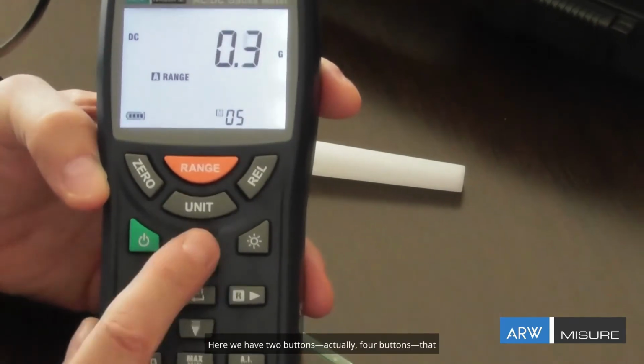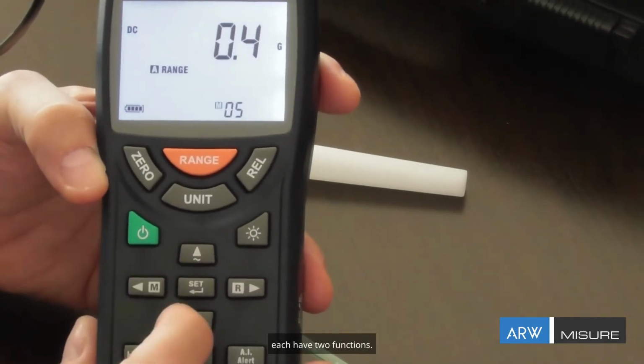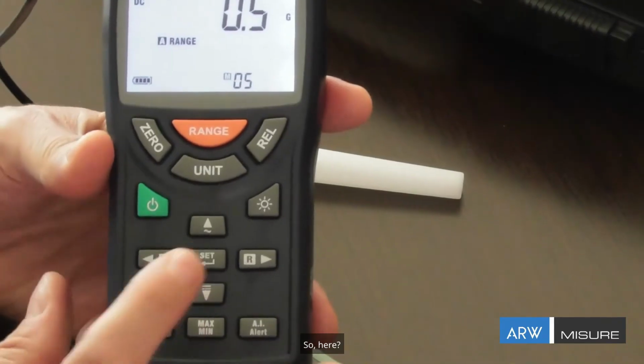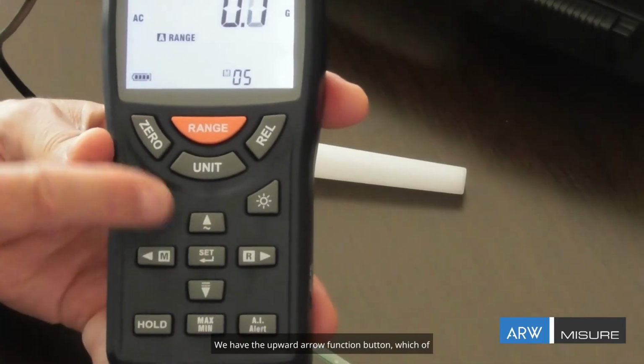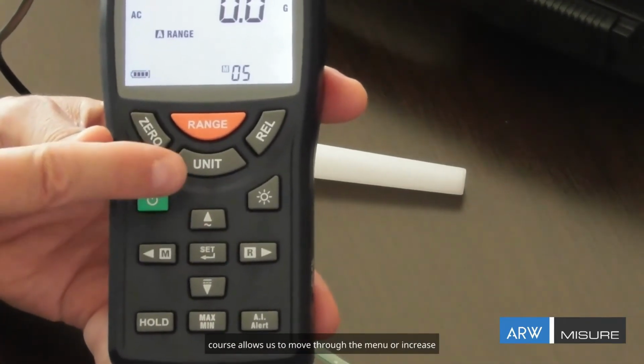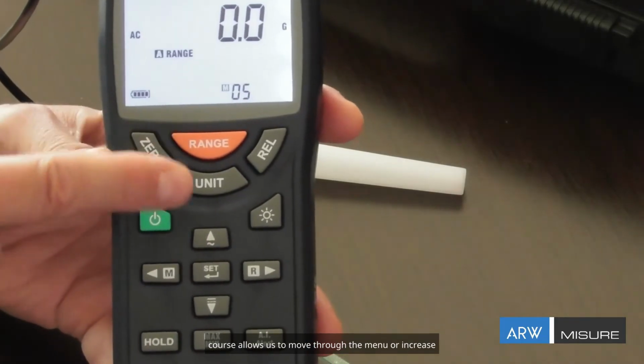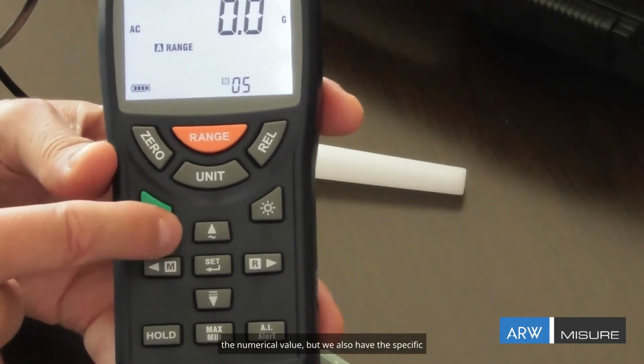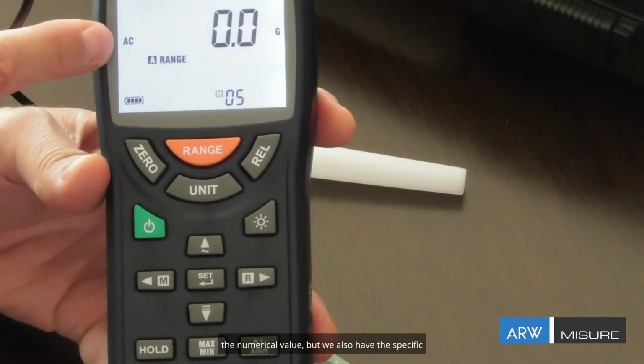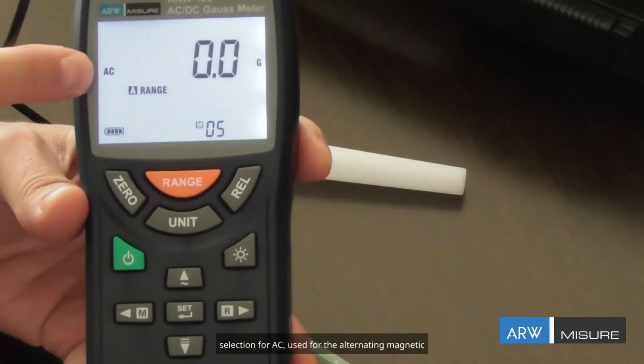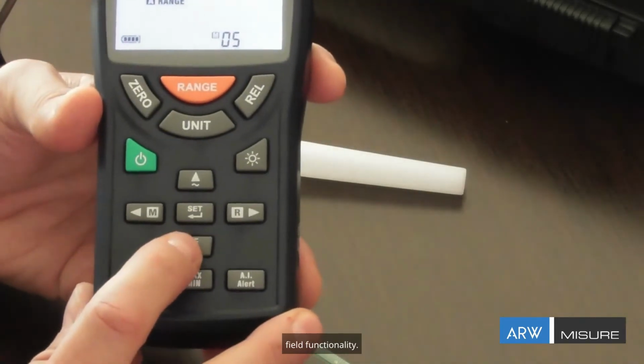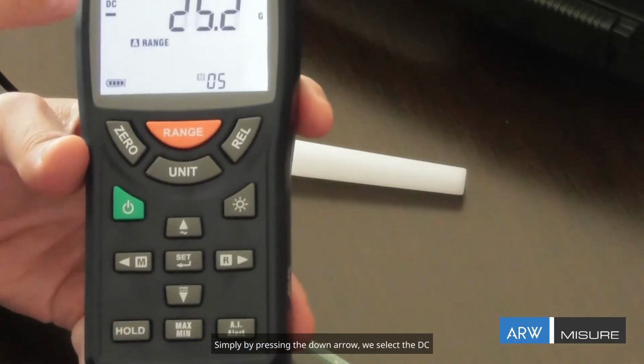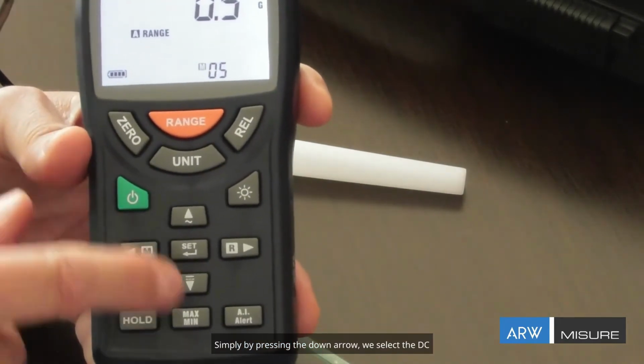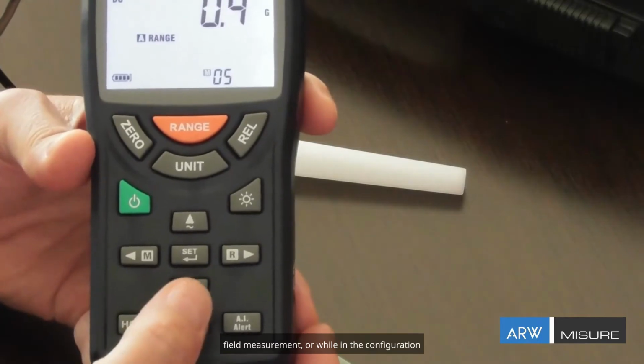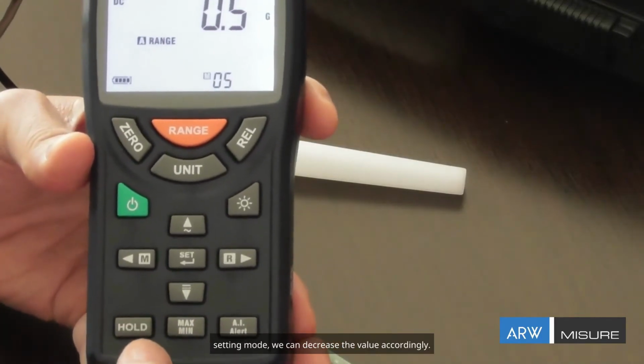Here we have 2 buttons, actually 4 buttons, that each have 2 functions. The upward arrow button allows us to move through the menu or increase the numerical value, and also provides the specific selection for AC, used for the alternating magnetic field functionality. Pressing the down arrow selects the DC field measurement, or while in configuration setting mode, decreases the value accordingly.